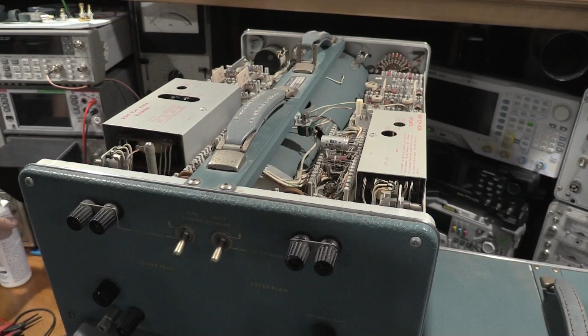Been doing the troubleshooting, taking a look at this, and through the back of the unit, there is a way to get in and view the back of the CRT. And the back of the CRT is not glowing, so that does confirm we have a filament problem. The CRT is not getting hot, so it's not boiling electrons off that it can then smash into the phosphor at the front of the screen. And what's very odd in this case is both guns are dead. I'm not getting any filament action on the upper or lower gun, and my 6.3 volts is there.